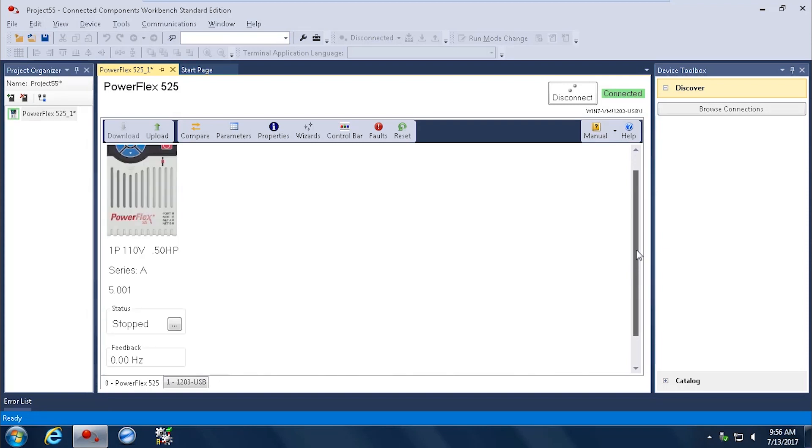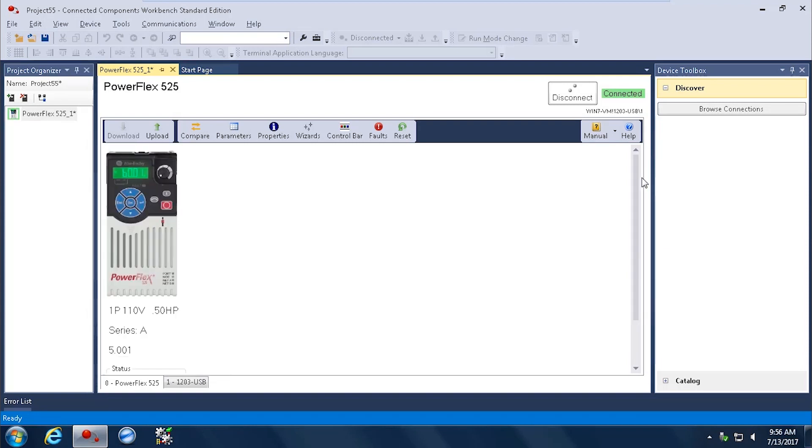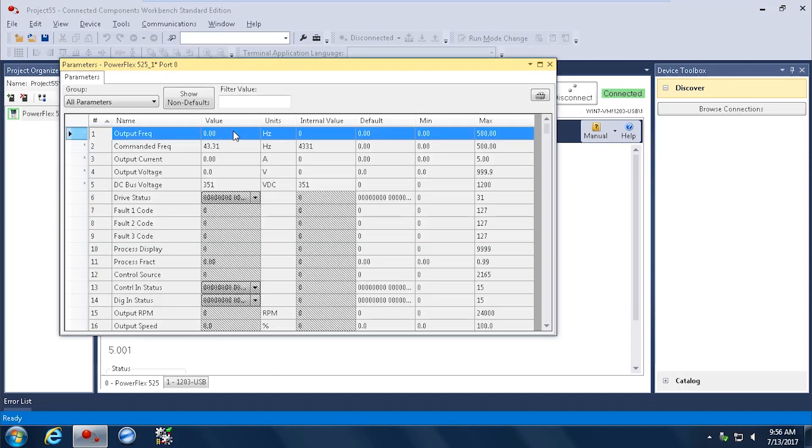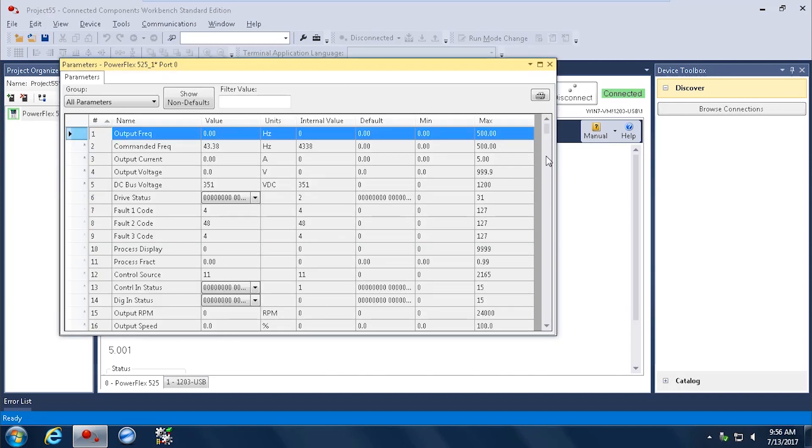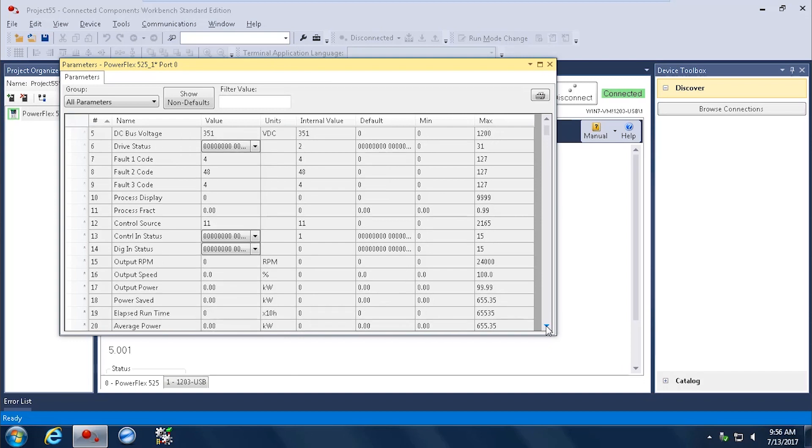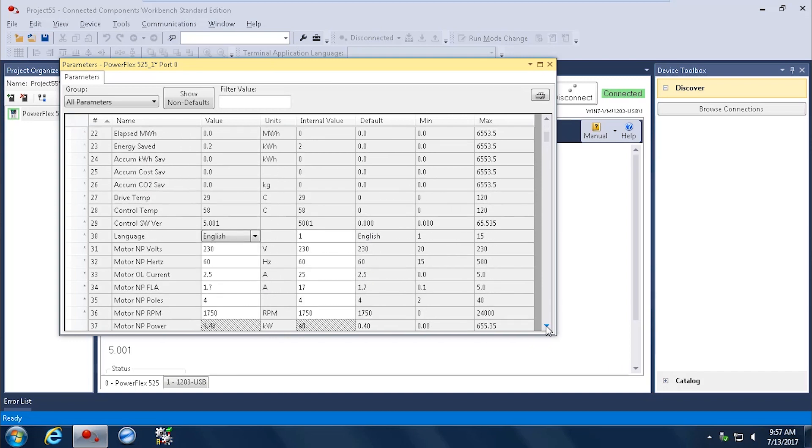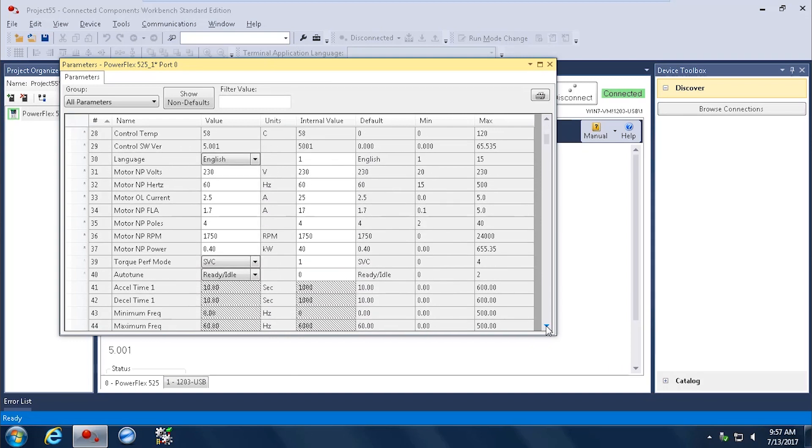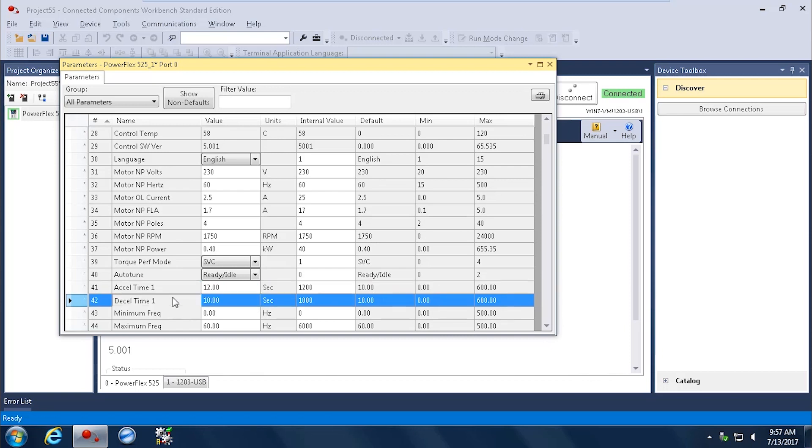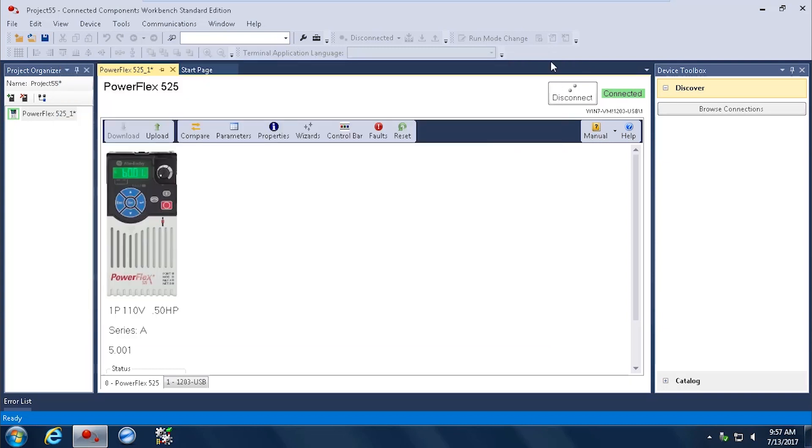There's a toolbar available to you to go ahead and look at different things. In this case, we're going to look at the parameters. All your drive's parameters are now available, and you can scroll down and see them all. In this case, we're going to select Accel Time 1, and we're going to change it from 12 seconds to 20 seconds. And we are connected to the drive right now. So right now on that drive, it's live 20 seconds.